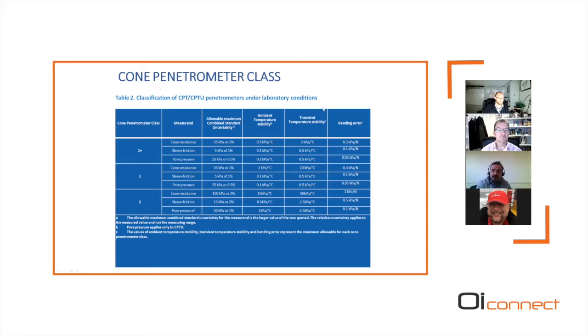The first, as we were saying, is the cone penetrometer class. So we introduce a series of classes within the measuring system, class 1+, 1, and 2. And we give clear requirements for the calibration in an accredited laboratory for each one of the sensors of that cone. In addition, the committee has acknowledged the large influence that temperature has on measurement systems, especially on strain gauges, and that's why we introduced two entries, which regulate how the cone will cope with temperature changes, because that can cause large drifts and have a big impact on the results.